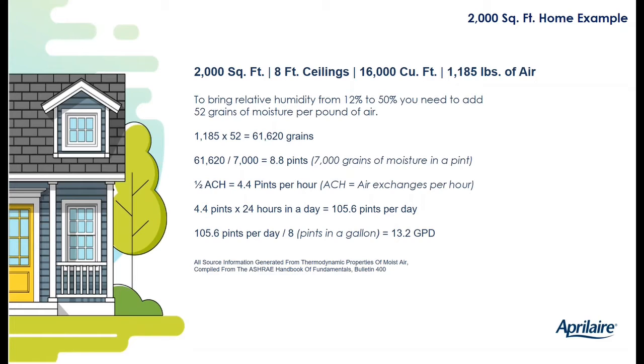Let's say you've got a 2,000 square foot house. Let's assume 8-foot ceilings. So that's 16,000 cubic feet, 2,000 times 8. That works out to 1,185 pounds of air. If we wanted to raise the humidity from 12% to 50%, you need to add 52 grains of moisture per pound of air. That's just off the psych chart. So you take the pounds of air, 1,185 times 52, you get 61,620 grains. What's a grain? Well, there's 7,000 grains of moisture per pound or pint. A pint of water is the same as a pound.